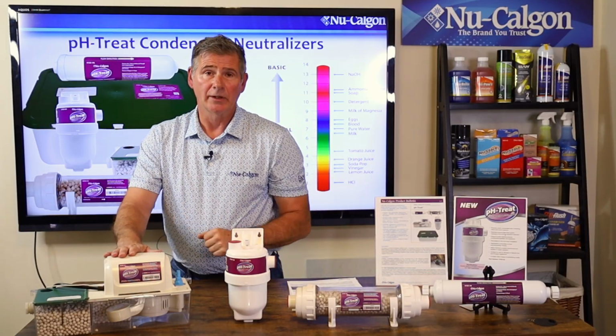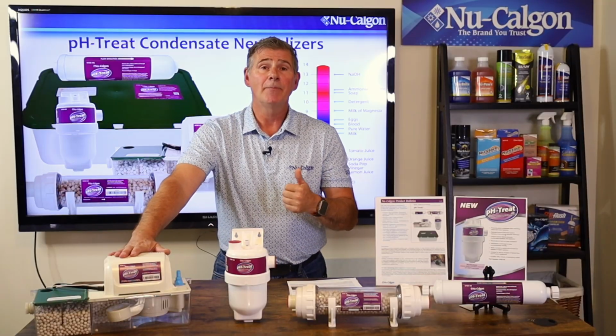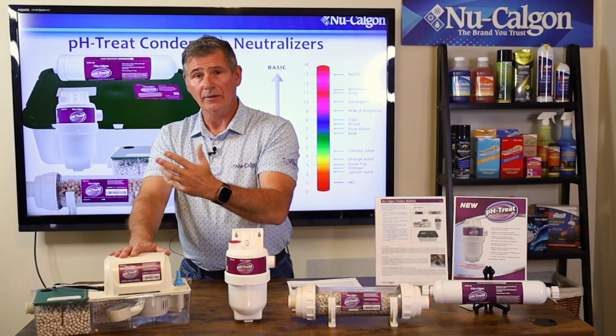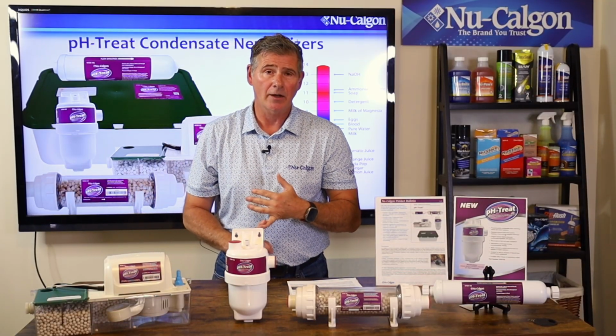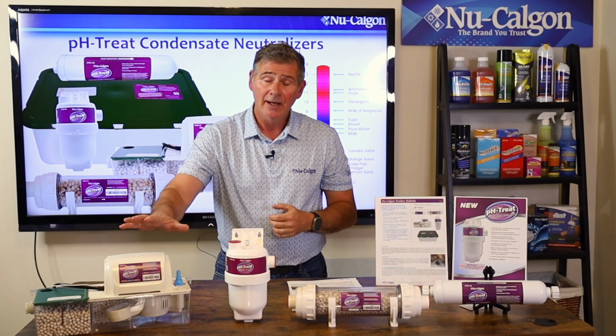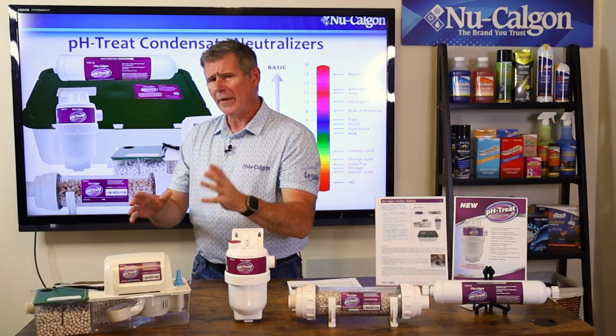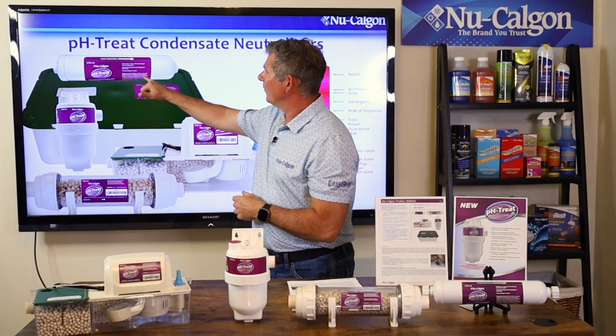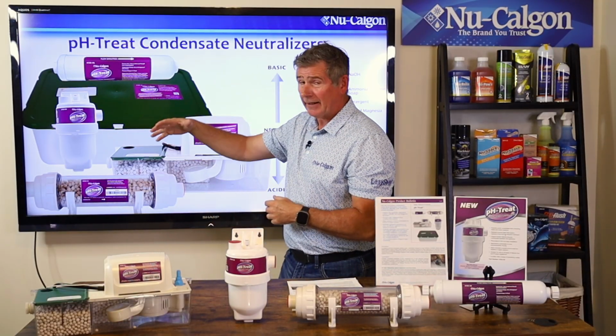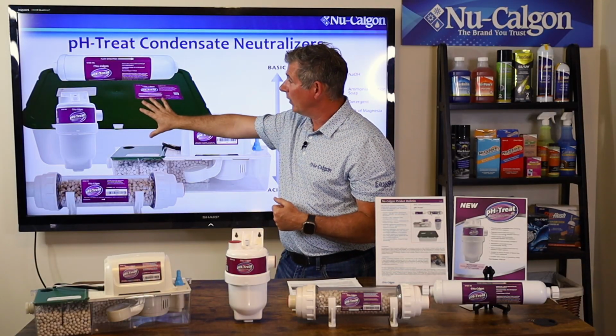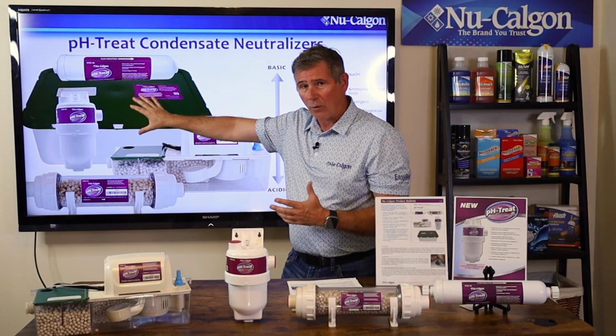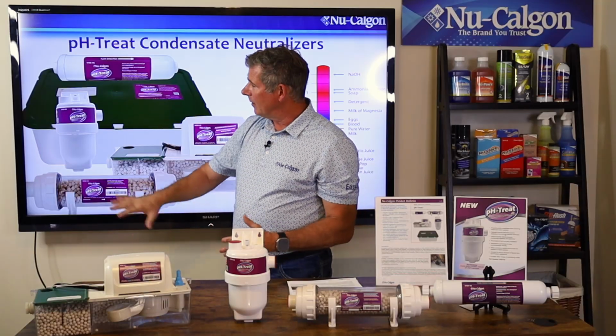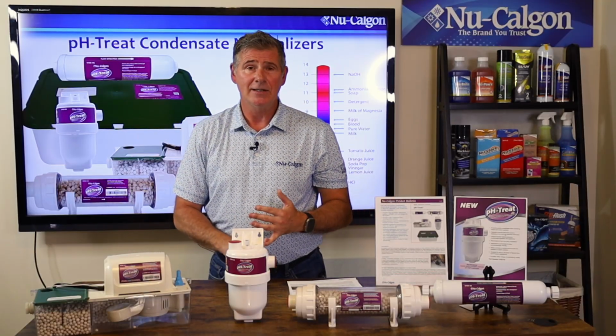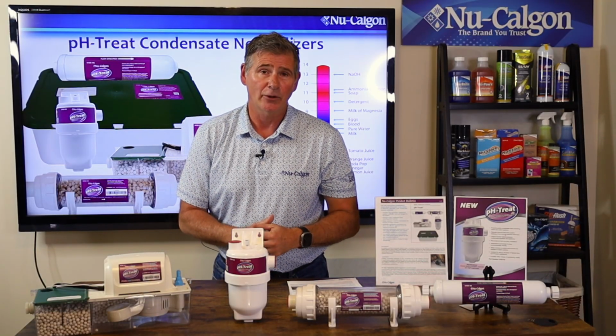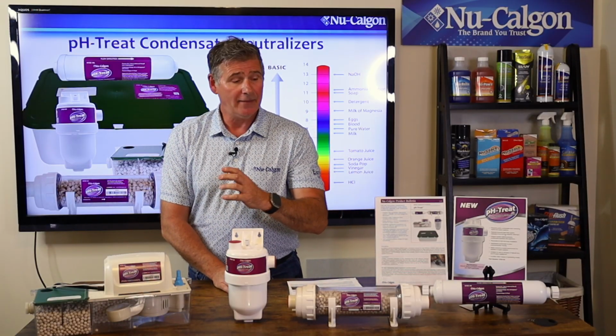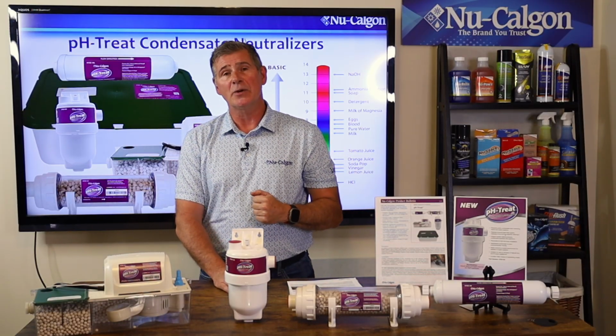So another really nice option if you're looking for a condensate pump and you need something that has the media on the inside to neutralize that condensate water from your high efficiency appliances, we've got you covered here. And then the one that I don't have is this large green one here. It basically looks like a container that you'd get at the container store. This one also has the media on the inside. It's for horizontal use only. It's going to sit on the floor. But this one will do up to a 3 million BTU system, or 20 gallons per hour worth of condensate flow. Okay, that kind of takes you through the lineup of pH Treat from NuCalgon.